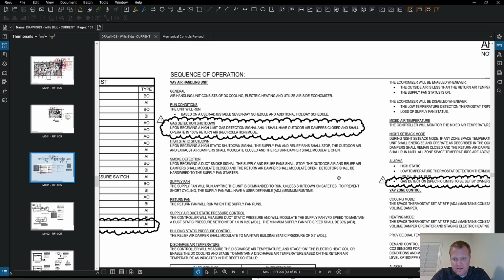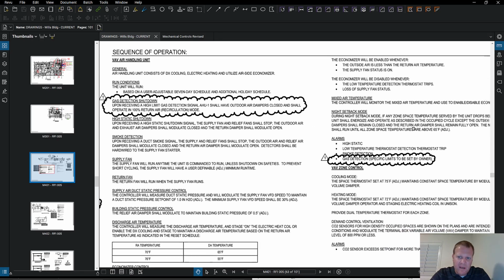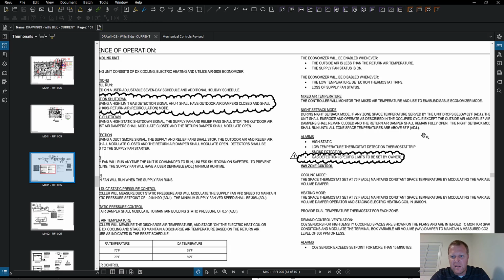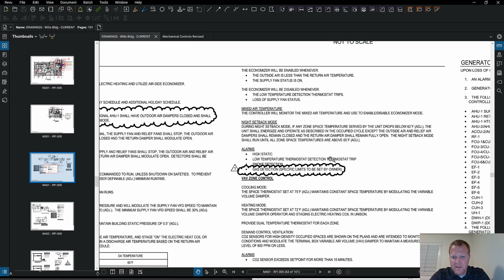Running through all these little things. Testing the setback mode, meaning when you go to nighttime, right? They're going to have a little sequence that says, okay, trip the timer, make it say that it's now nighttime mode, and let's watch the system on its own go to that mode. And if it doesn't, then you're going back to the pre-functional testing and figuring out why it didn't do that, or reprogramming or whatever. Hopefully that made sense as far as what the functional performance testing is trying to do.